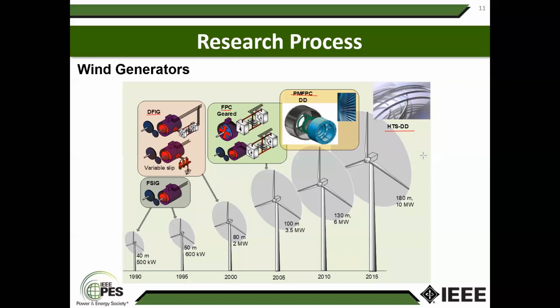Dogger Bank will most probably use the permanent magnet full power converter type. There is a Vestas machine right now, each rated at 8 megawatts, which will most probably be the one used. So wind generators are frequency independent, meaning we can have any frequency on our aggregation grid without restriction.